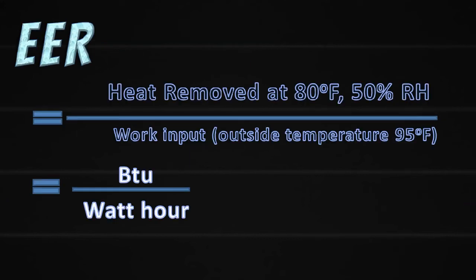Now let's see what is the energy efficiency ratio. Before that, let's understand that the COP of a refrigerator is not a practical measure for comparing the performance of any refrigeration unit. COP depends on the temperature of the system and surroundings, and hence to compare two refrigeration units, these temperatures have to be fixed. That is exactly what is done in EER. EER is itself a COP with fixed inside and outside temperatures and humidity.